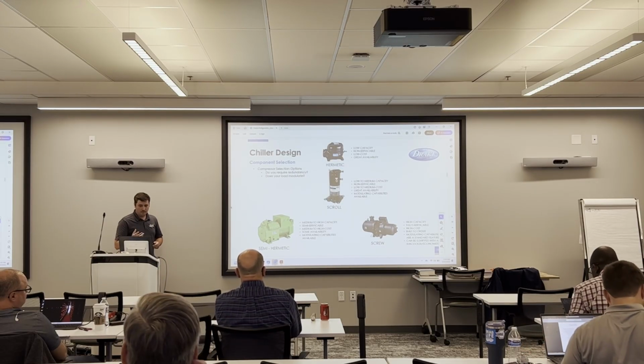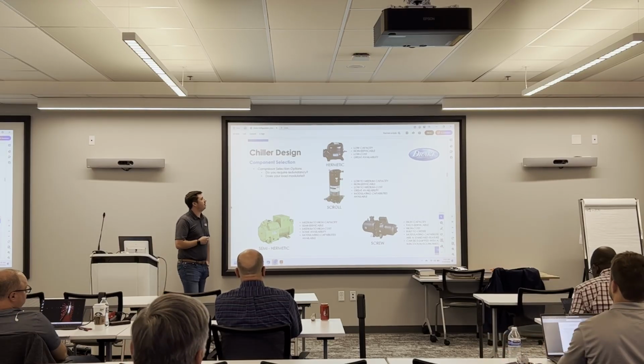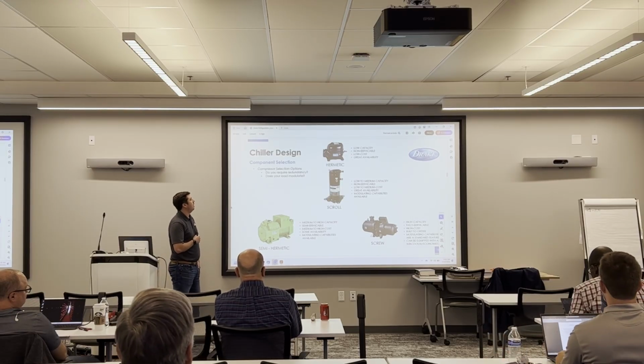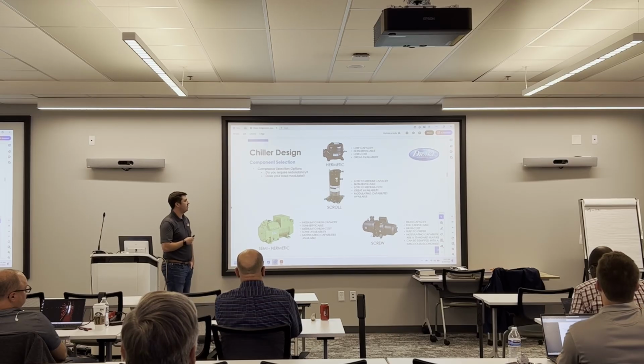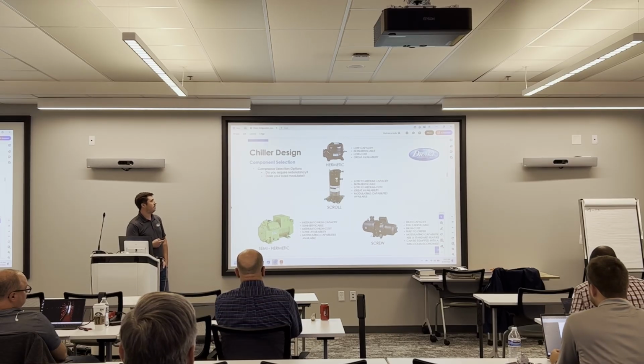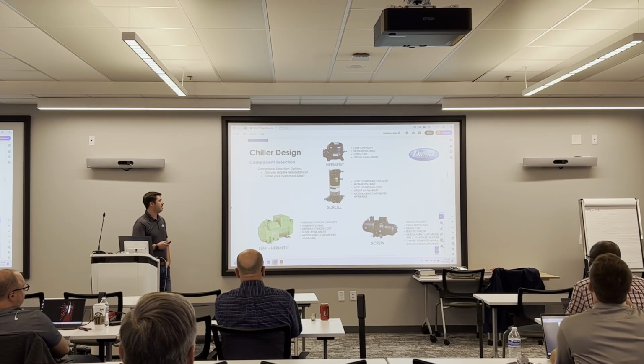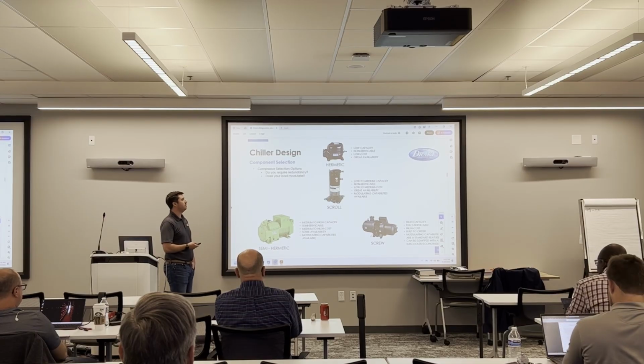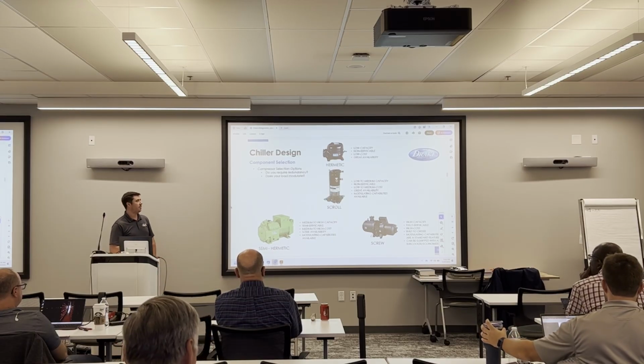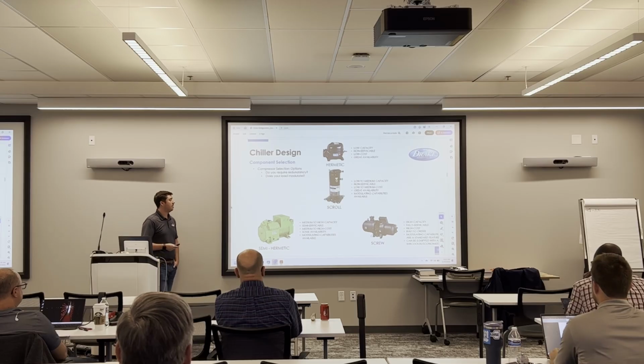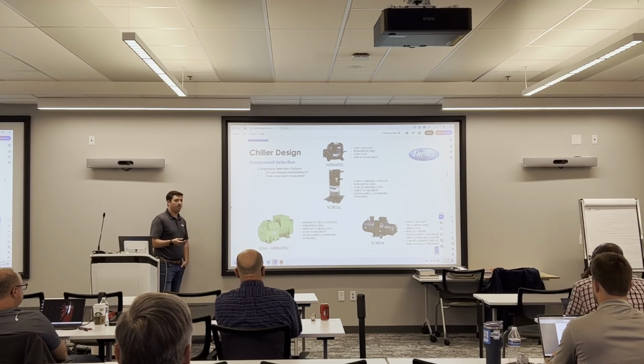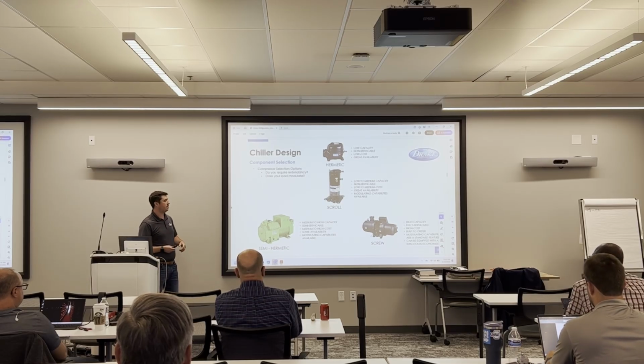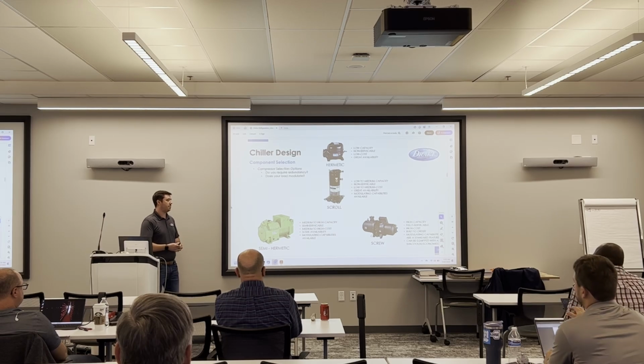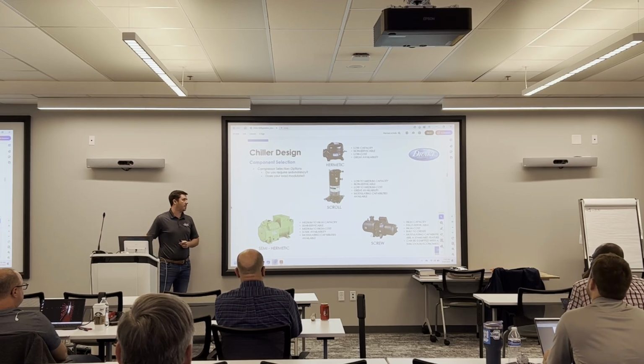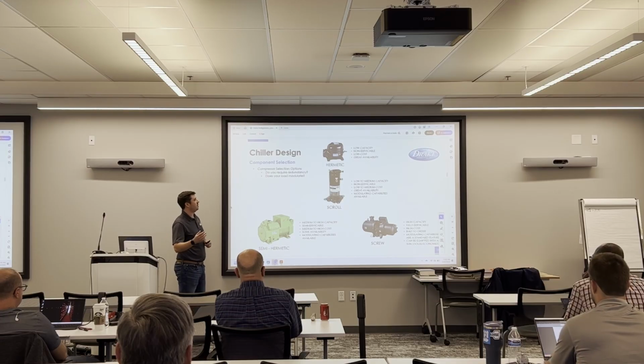All right, I just want to throw up a couple different compressors up here. We can talk through each one. Some questions we ask after we've figured out what size compressor we need: do you need any sort of redundancy? These chillers are critical. You don't want to have a compressor fail on you and then not be able to cool your process. By redundancy I mean, do you want a second compressor on that same chiller circuit? If one goes down, you can service it, but you still have a second compressor on that same chiller that can take up the mantle and keep the process going.